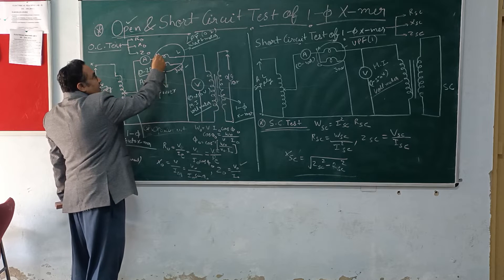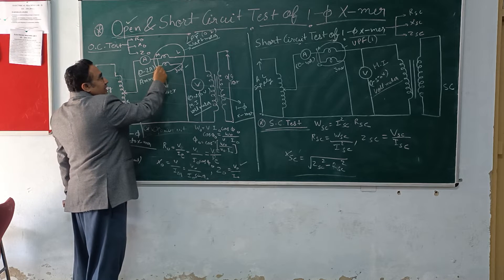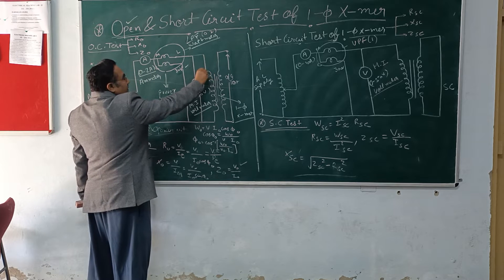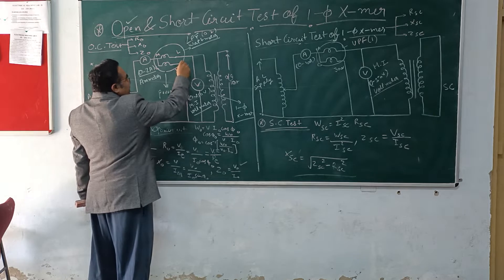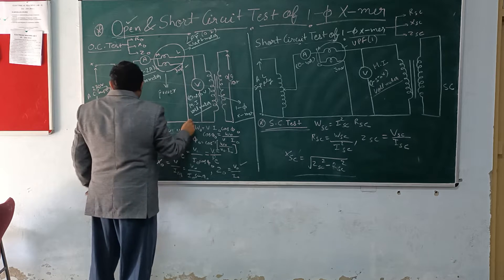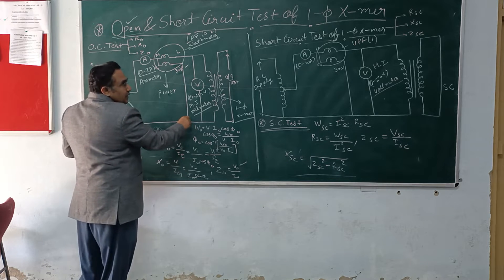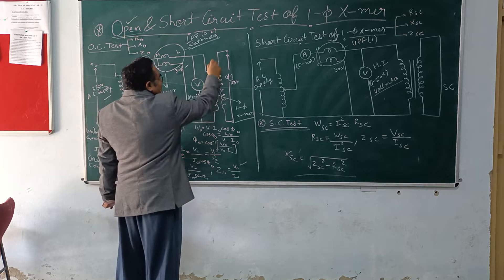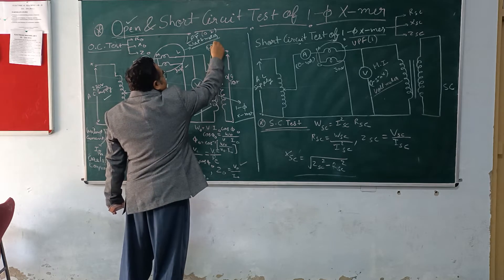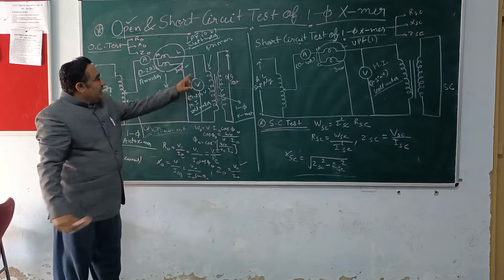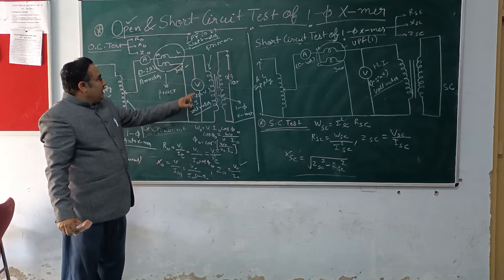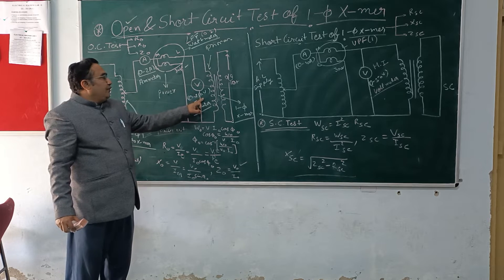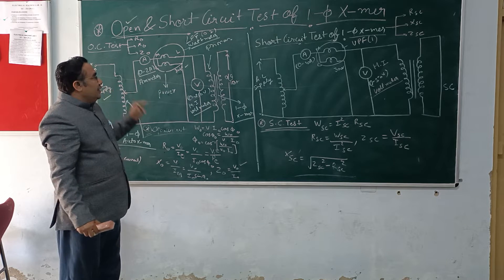How are connections being made? M and C are being short circuited. M is connected to the transformer primary one end, and this 300 volt terminal is again connected to the autotransformer neutral end. After making this connection, this is the primary winding of the transformer. We are measuring this voltage across the primary winding through a voltmeter, which is of range 0 to 250 volt, because the maximum voltage we are applying is 220 volt.